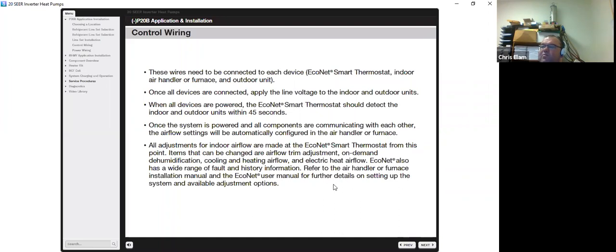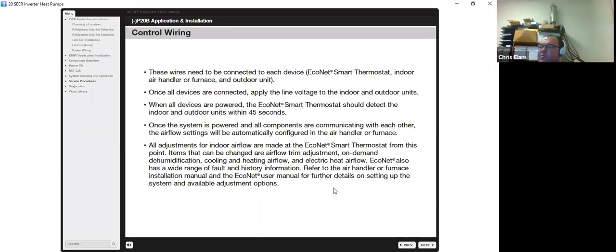The EcoNet also has a wide range of fault and history information. It will give you specific, exact faults, fault codes, which we'll get into on the second webinar. Because your outdoor unit, in some cases, will give you a generic fault, whereas your EcoNet will give you a specific dedicated fault. So you know exactly what the problem is, instead of hunting around for a generic fault.